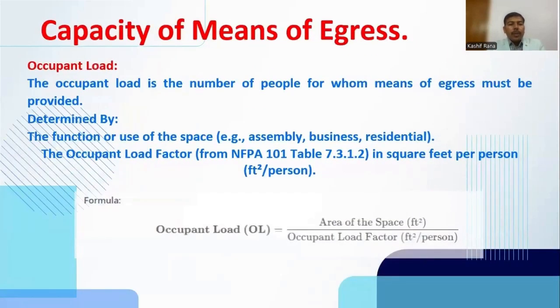50 occupants. What is the occupant load? Occupant load is the number of people for whom means of egress are provided. We can calculate it with this formula. Occupant load is equal to the area of space divided by the occupant load factor. The occupant load factor is constant and defined in NFPA 101. The table is mentioned over here.